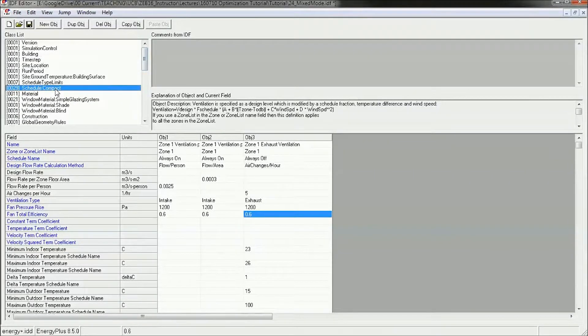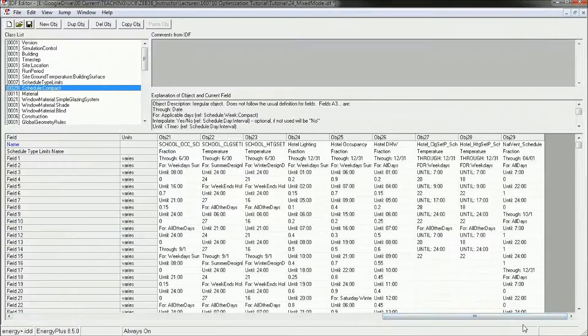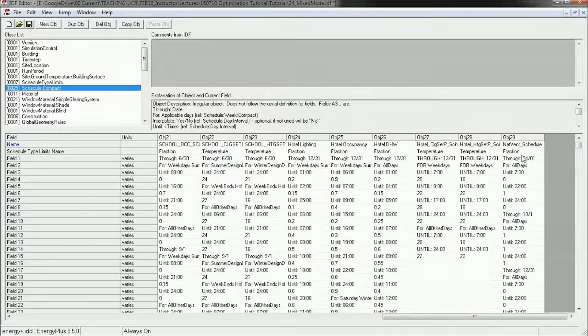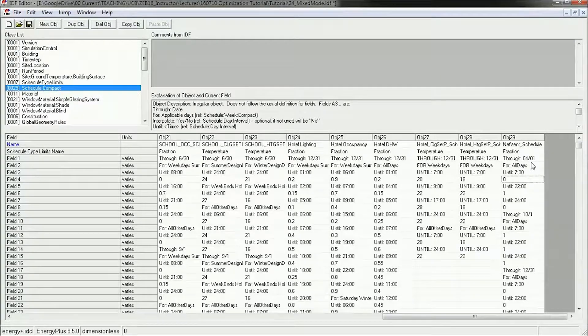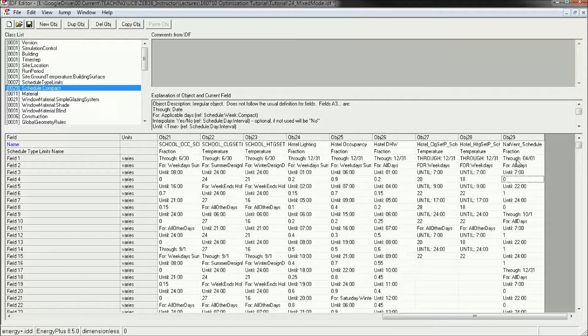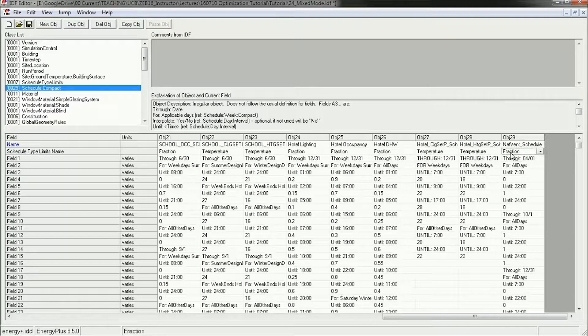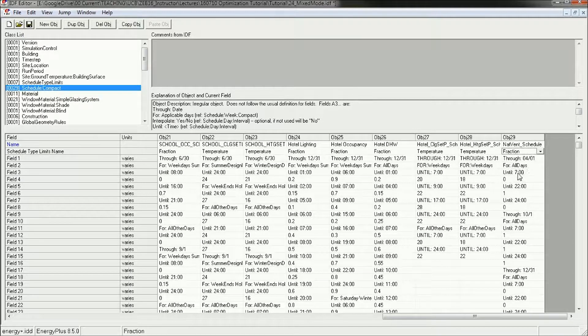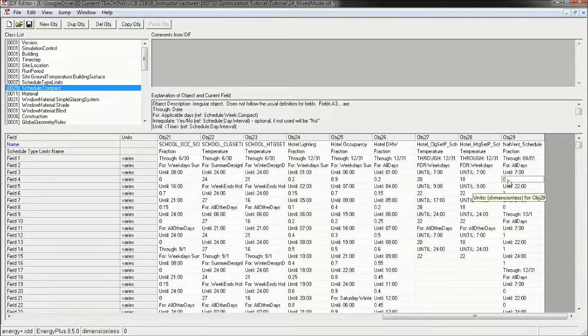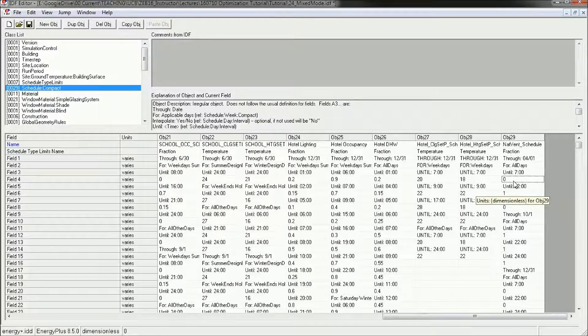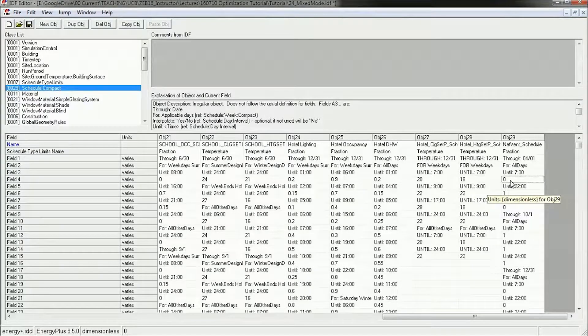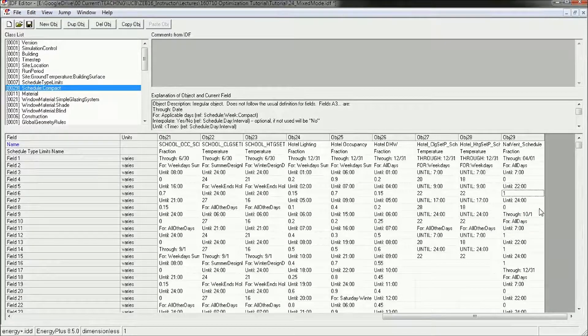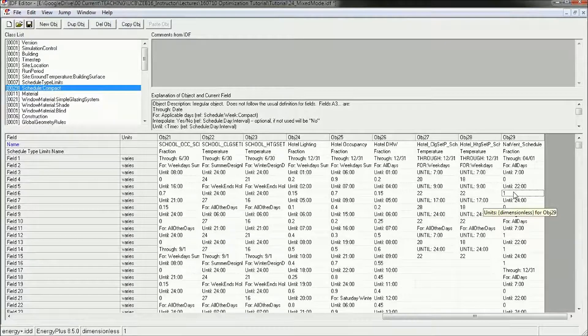So back to schedule, we want to create a slightly more complex schedule. And this natural ventilation schedule already has some complexity into it, programmed into it. It says that it's a fraction. So it's going to give you a fraction of the opening area from January 1st to April 1st for all days from midnight to 7 a.m. It's going to be 0, which is going to multiply it by 0, which would result in a ventilation opening of 0. It's going to go from 7 a.m. to 10 p.m. 1, which would result in a window opening of 1 times whatever your window opening is.